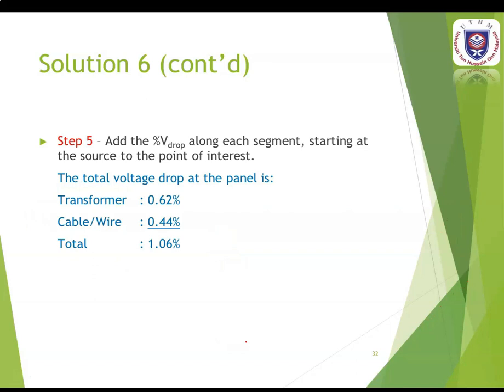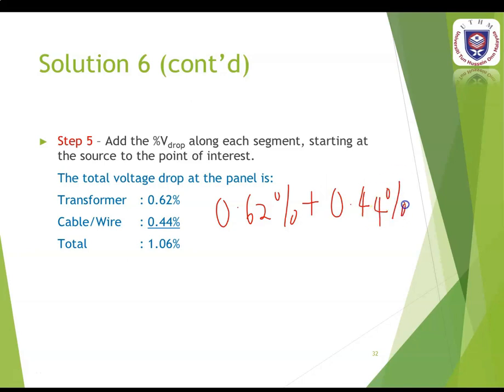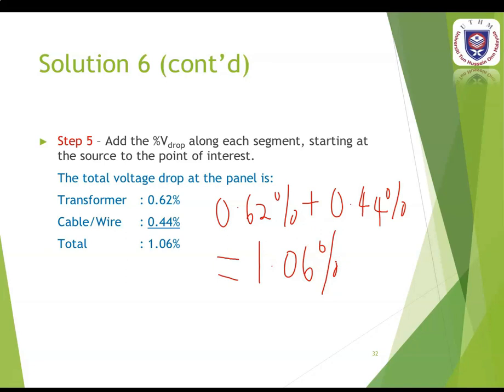The final step is to add all the voltage drops along each segment from the source to the load. The transformer contributes 0.62% and the cable or wire contributes 0.44%. The total percentage of voltage drop is 1.06% for the single-phase system.